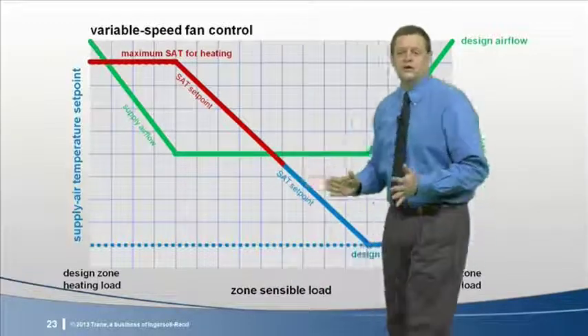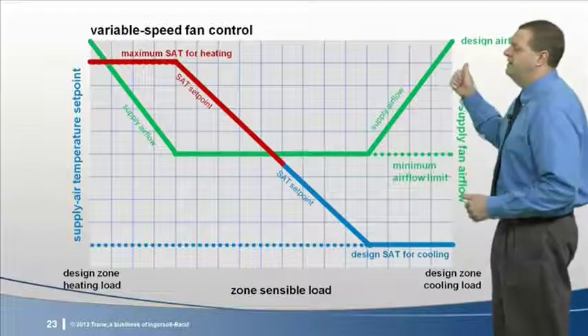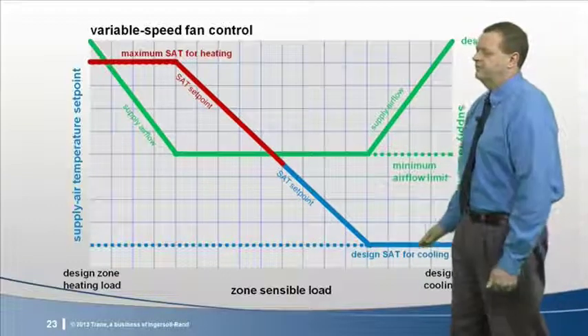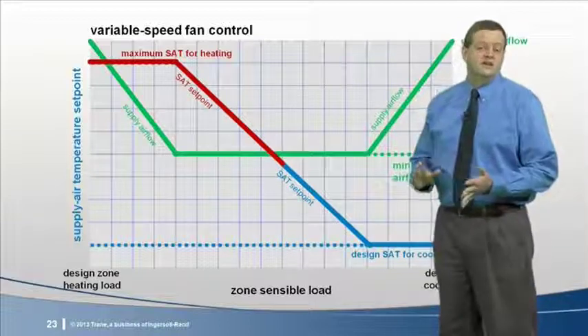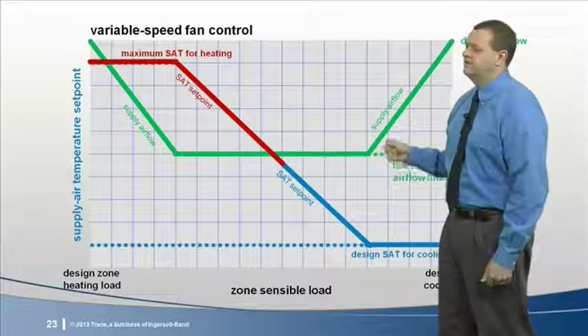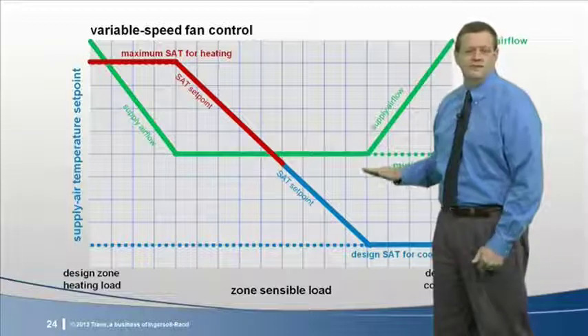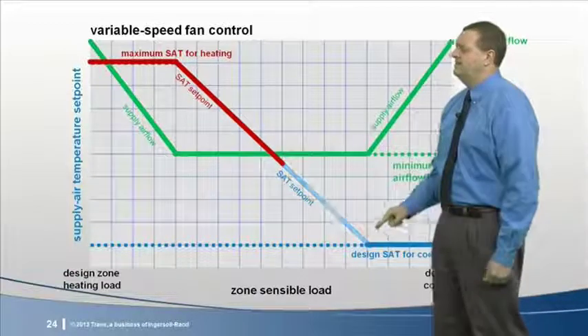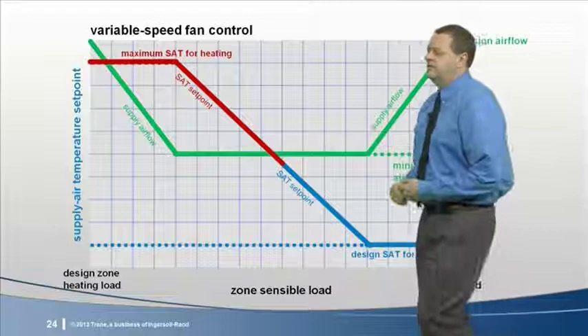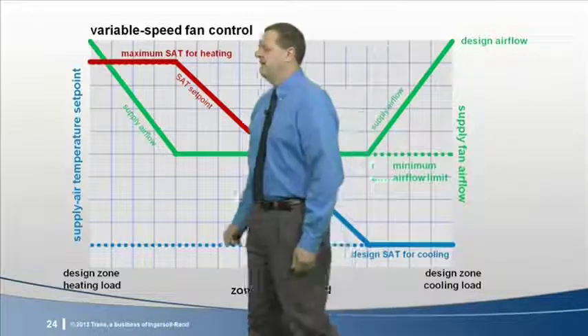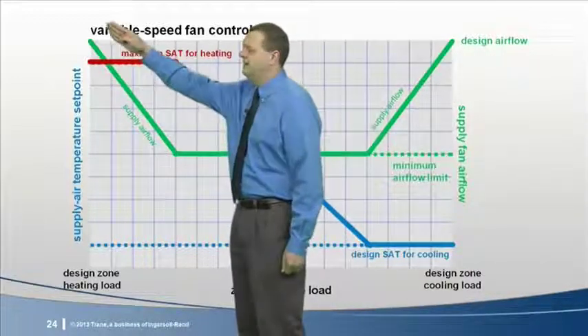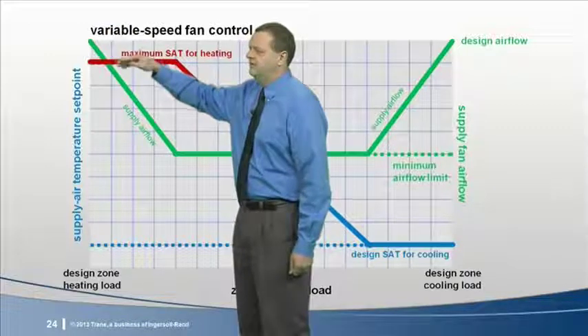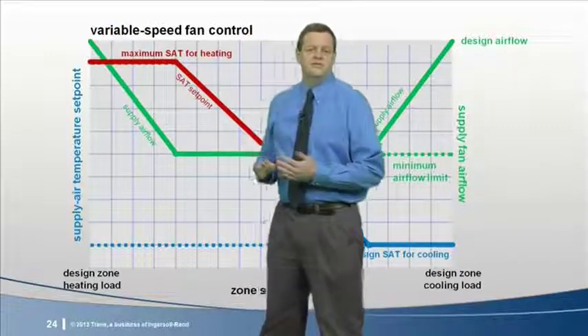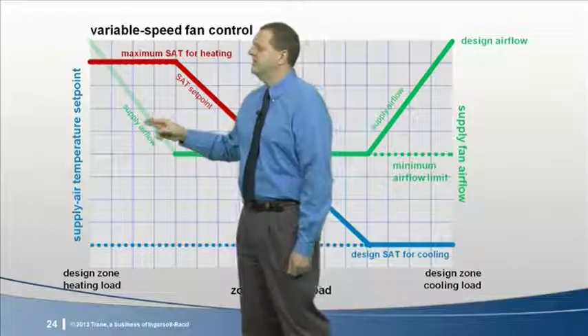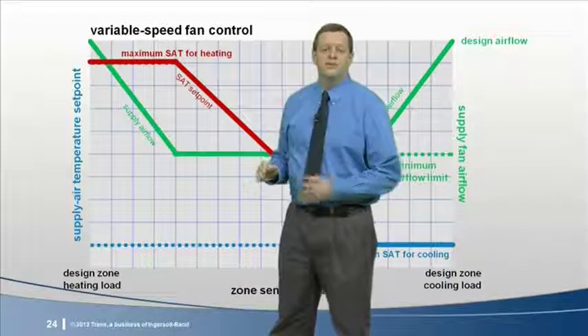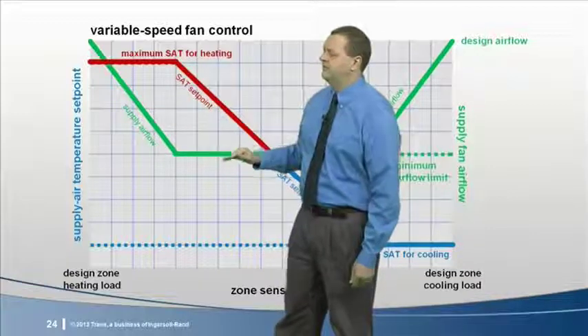So, at full cooling load, the system delivers design airflow at a cold temperature. But as the zone cooling load decreases, the system first reduces fan airflow until it reaches some minimum limit, and then raises the supply temperature set point. Same thing when the zone requires heat. At full heating load, the system delivers high airflow at a warm temperature. And as the heating load in the zone decreases, it first reduces supply airflow and then lowers the supply temperature once the airflow reaches this minimum limit.